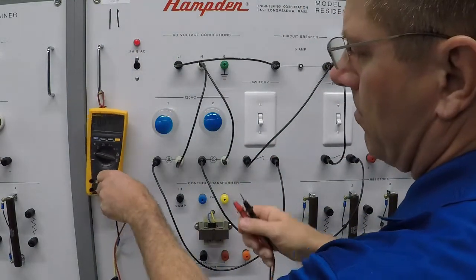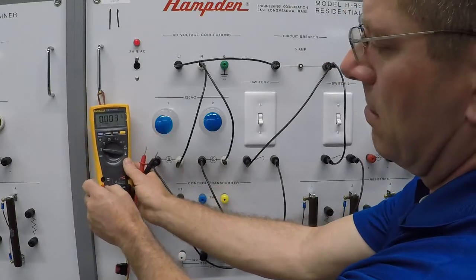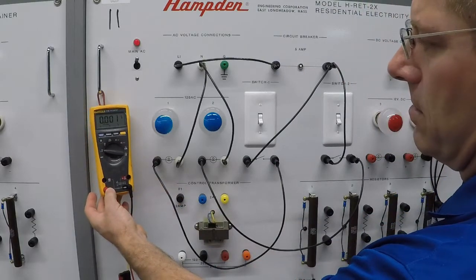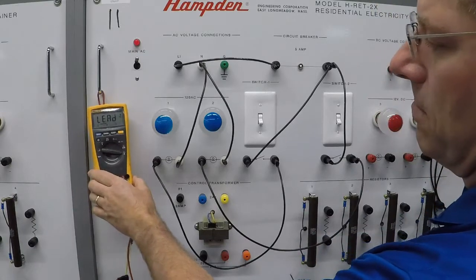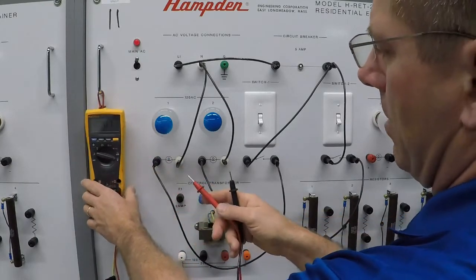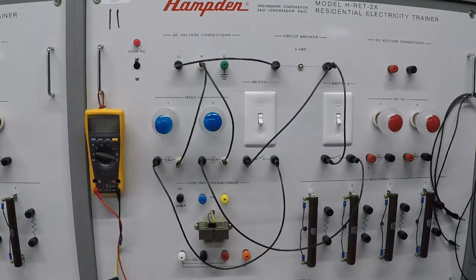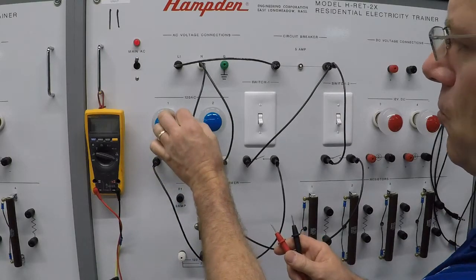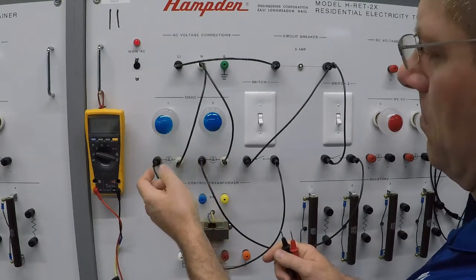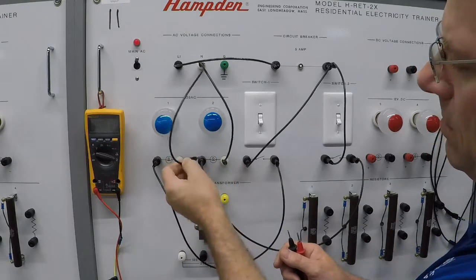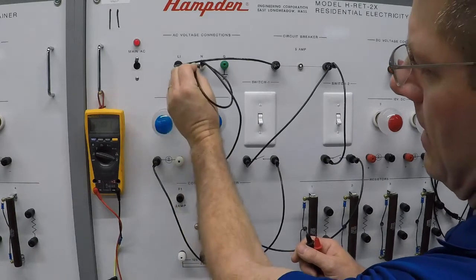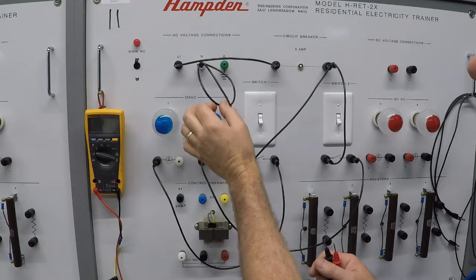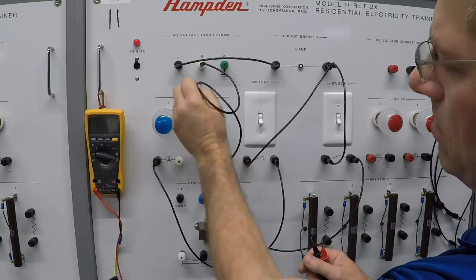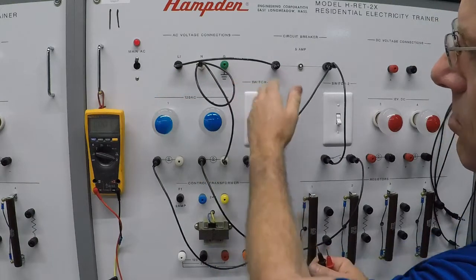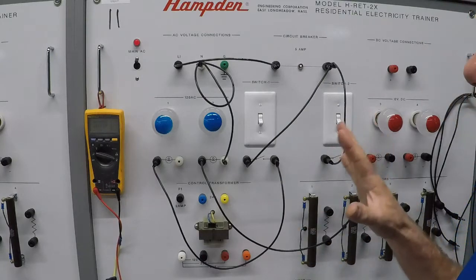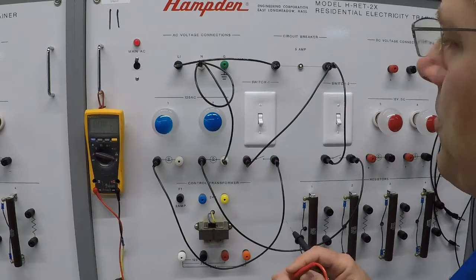connect our meter properly. So we have to switch our lead from voltage and resistance to current. We have to change the meter position to AC amps. And now we can connect the meter within the circuit. I'm going to remove the neutral line from the circuit. I will disconnect it from the light bulb, plug it in up here at the neutral connection. That way we do not have this loose dangling where it might touch the board. Remember, you're working with 120 volts AC. Severe damage to the board or injury to yourself could result.